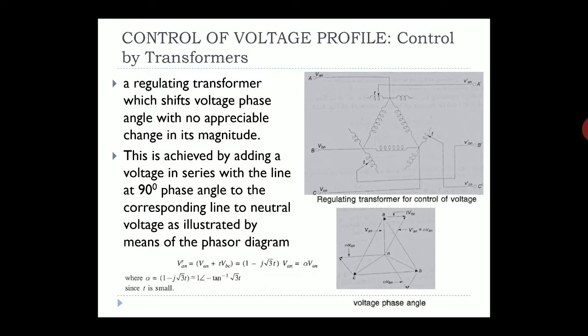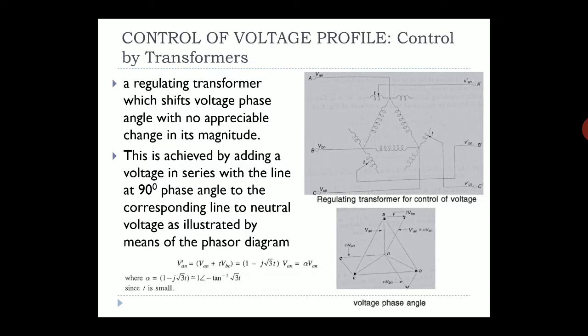Now we will see the voltage angle control. A regulating transformer which shifts the voltage phase angle does so with no appreciable change in its magnitude. This is achieved by adding a voltage in series with the line at a 90-degree phase angle relative to the corresponding line-to-neutral voltage, as can be seen in the phasor diagram.